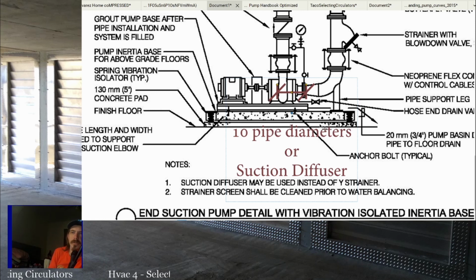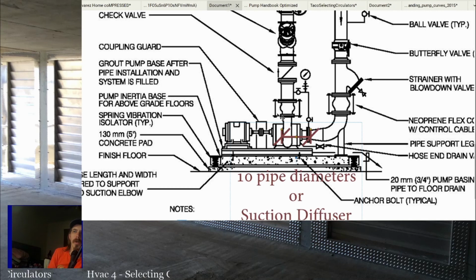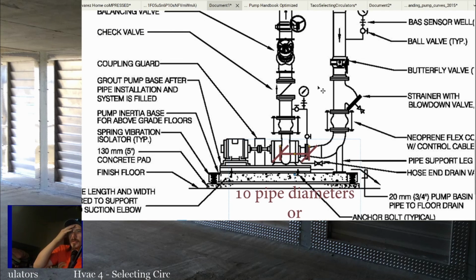And what happens if the suction diffuser clogs up or the strainer clogs up? Your pump cavitates. So on end suction pumps, generally they don't do this 10 pipe diameter. They'll always have a suction diffuser before it. But if you don't have a suction diffuser, you need at least 10 pipe diameters before the inlet of the pump. On the outlet of the pump, when you come out of a pump, another flex connector is a good idea. What they're showing right here is a gauge so that you can read the pressure before and after the pump. That's nice, but it's really only needed on bigger systems. I wouldn't bother most of the time with smaller ones unless you just like adding stuff.